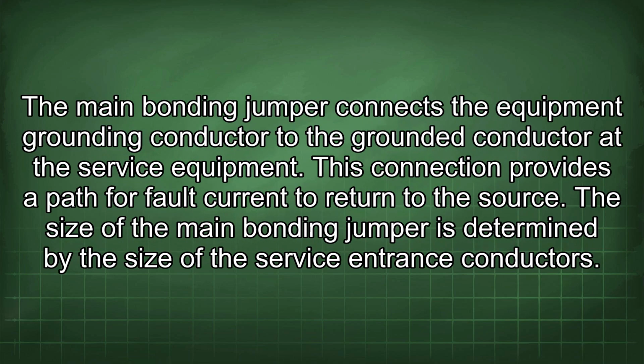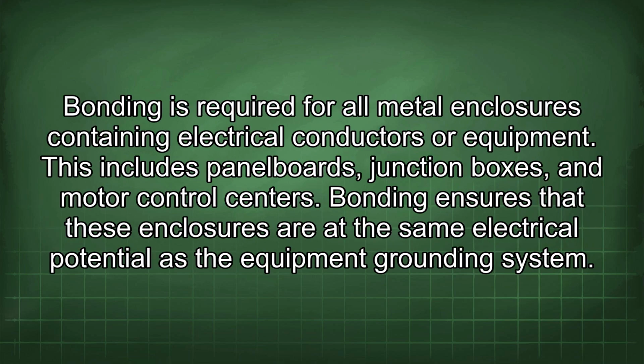The main bonding jumper connects the equipment grounding conductor to the grounded conductor at the service equipment. This connection provides a path for fault current to return to the source. The size of the main bonding jumper is determined by the size of the service entrance conductors. Bonding is required for all metal enclosures containing electrical conductors or equipment. This includes panel boards, junction boxes, and motor control centers. Bonding ensures that these enclosures are at the same electrical potential as the equipment grounding system.